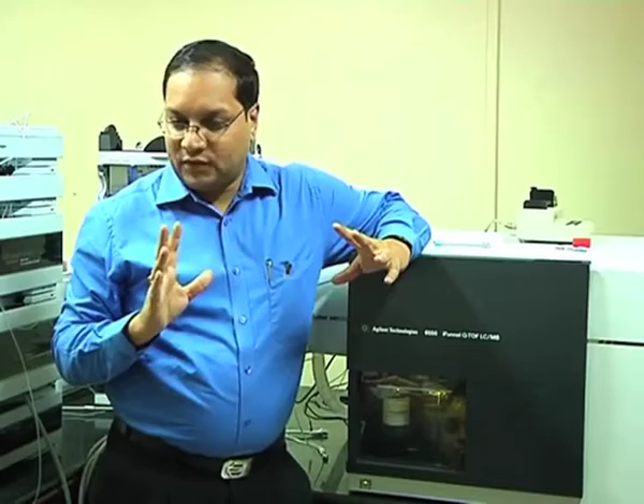It's also called a mass filter analyzer because of the way it behaves. Quadrupole is what? 4 rods. So 4 rods like this, positioned like this, at some length. So what is the logic? It is also called a mass filter. Why? Because it has the ability to filter mass. If you say look for mass of 500, it will filter everything away and only allow 500 to get inside the quadrupole and travel through the 4 rods.